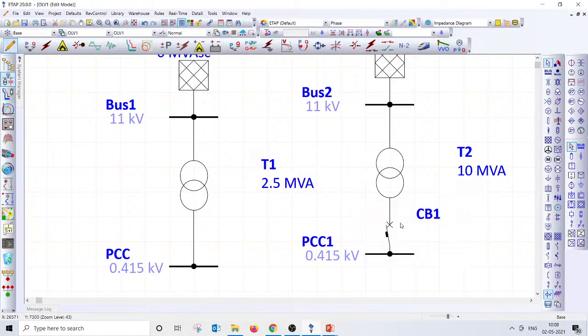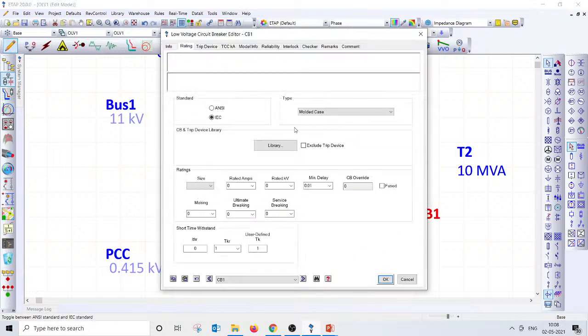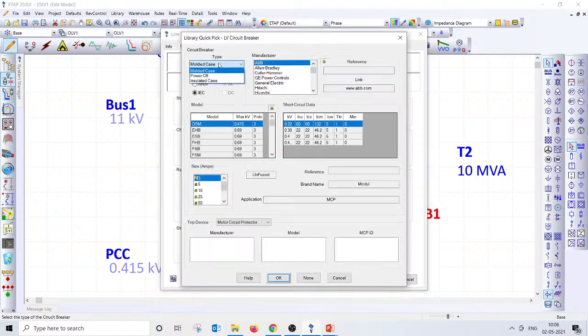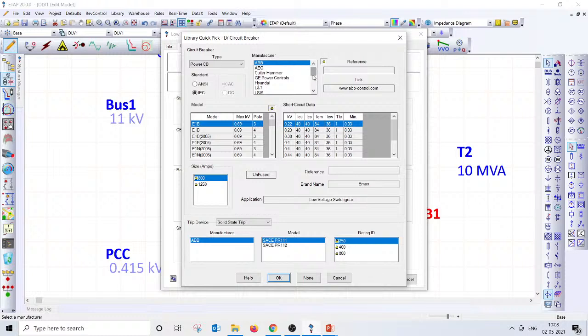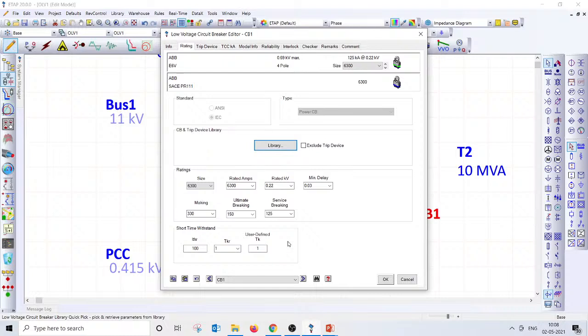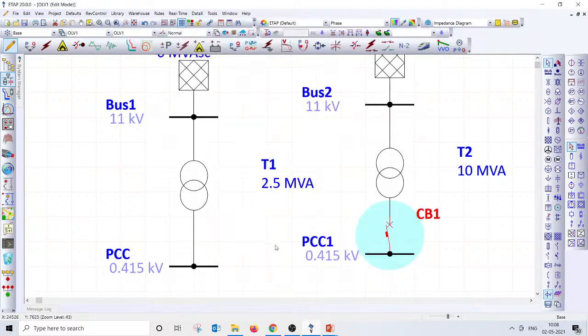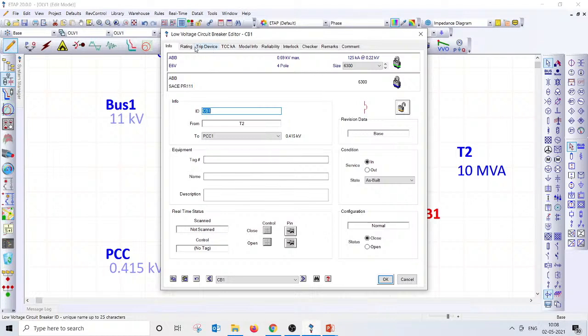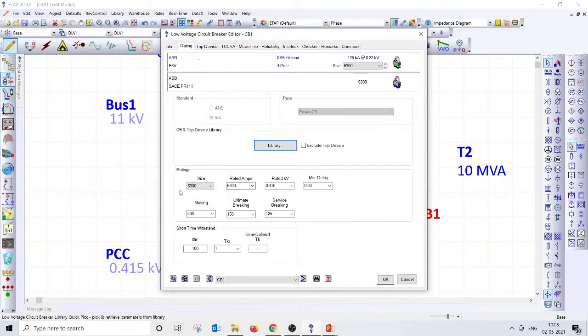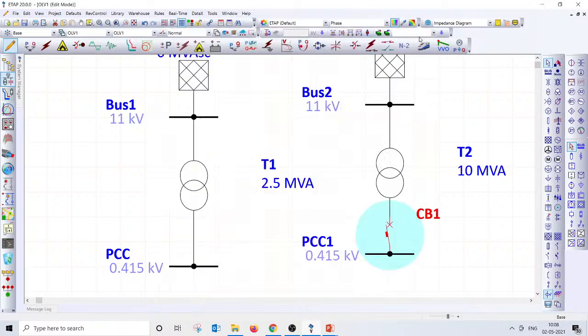So the continuous current rating which is available on the LV side breaker basically dictates what could be the maximum transformer rating which we can go with. If you take a power circuit breaker, you can go with reputed manufacturers and find out what's the maximum rating which is available, right? You can find breakers up to 6,300 amps, and I have never seen any breaker beyond 6,300 amps in 415 volt. So basically the 6,300 amps dictates or decides what could be the maximum transformer rating which you can connect.